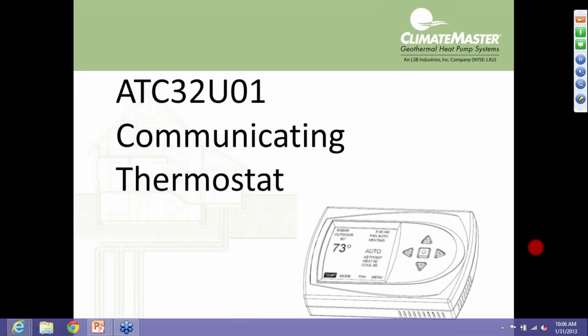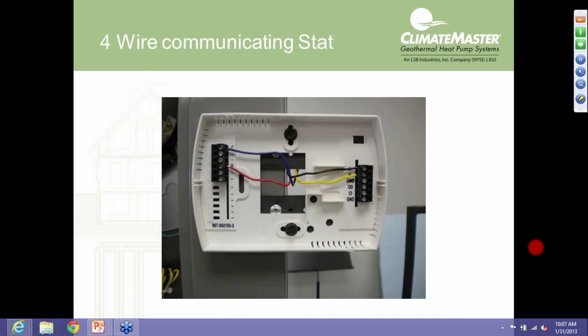Now, the thermostat is the ATC32U01 communicating thermostat. And again, it's only a 4-wire connection. So you can see here with the thermostat removed from the subbase, we got R and C for power, and then we got an A and B that's actually our communication going back to and from the thermostat to the DXM2.